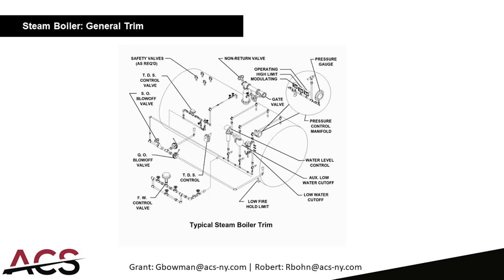The water level control gives a modulating signal to your feed water valve if you have a modulating feed water system, or a dry contact to start a pump otherwise. The low water cutoff is typically a float type, and you would have an auxiliary low water cutoff that is a probe type. For a typical high pressure boiler, you'll also have a non-return valve and a gate valve — all of these components are ASME pieces manufactured by the boiler manufacturer. In the upper right you have operating limit, high limit, and modulating controls, as well as your boiler pressure gauge.